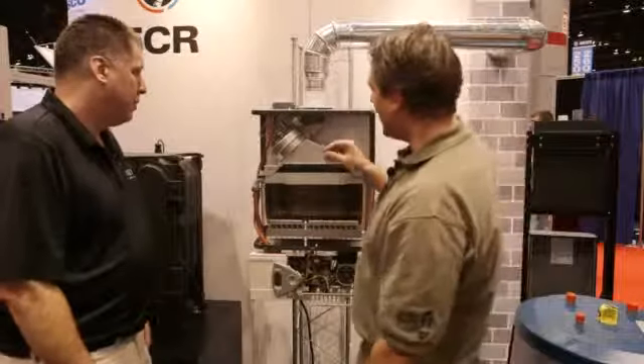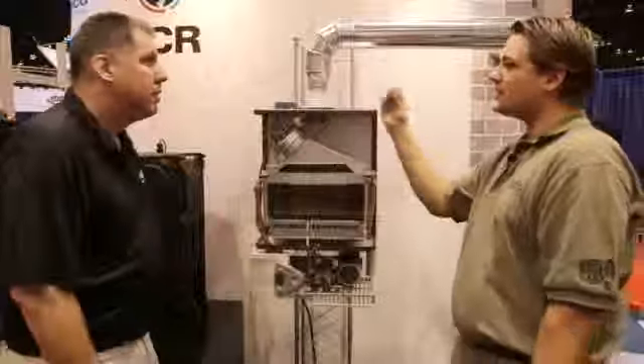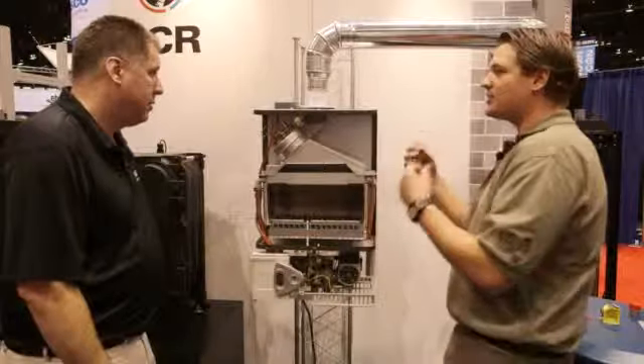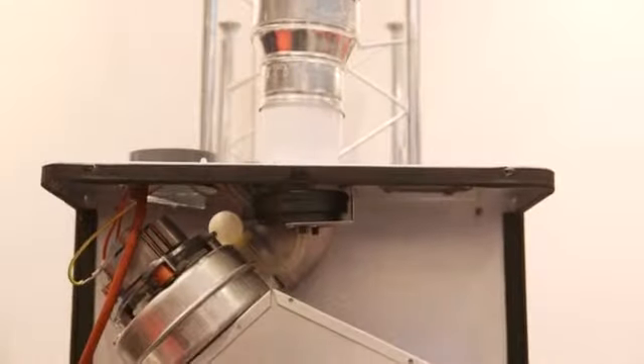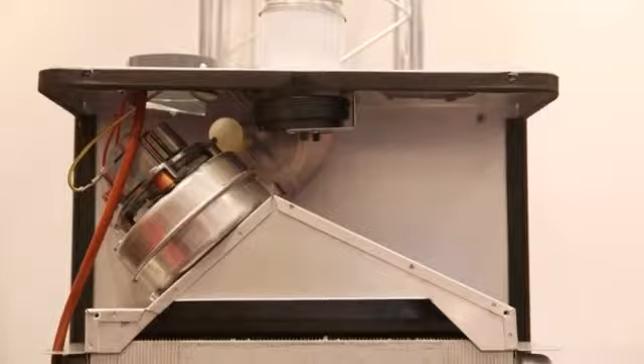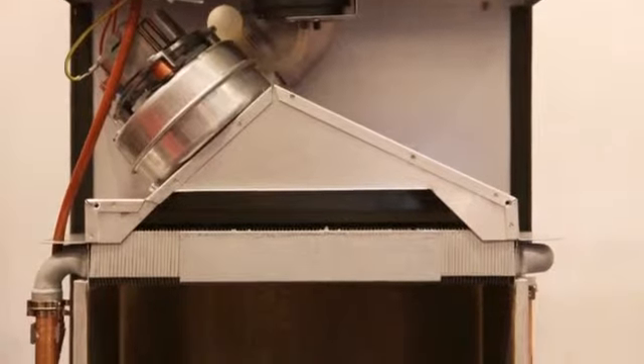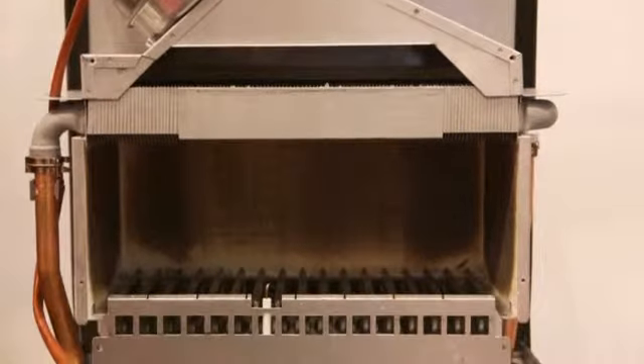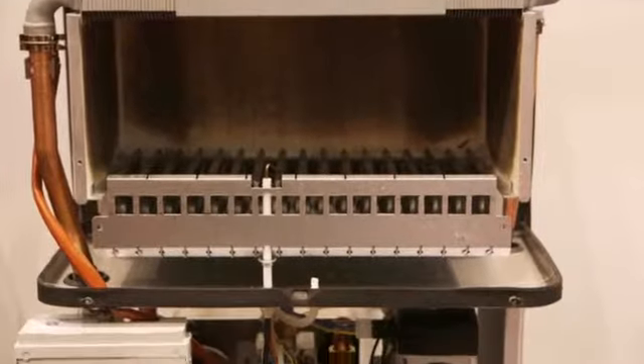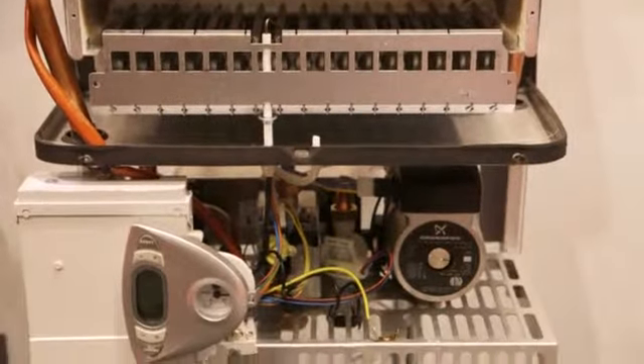The reason we can do that is if you look inside of here, you see this tube? I do. That goes to a venturi inside the fan. So it's actually measuring the draft that's in the chimney and modulating the fan around that draft. That's why you can vent it into a chimney. So it can regulate if you got a high draft or a low draft. Yep, it's going to modulate the fan off of that. What if I don't want to go into a chimney? I just want to vent directly to the sidewall. I can do that with this. You can do that with this as well.